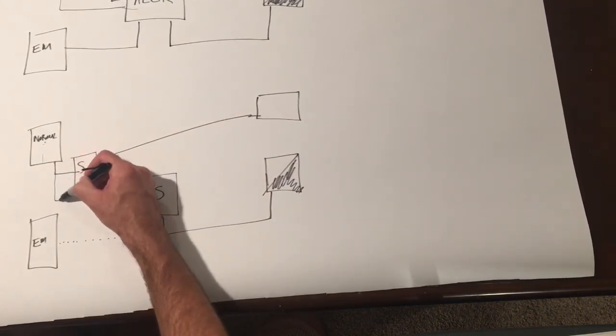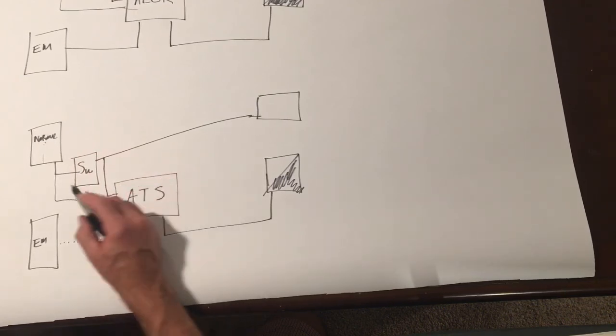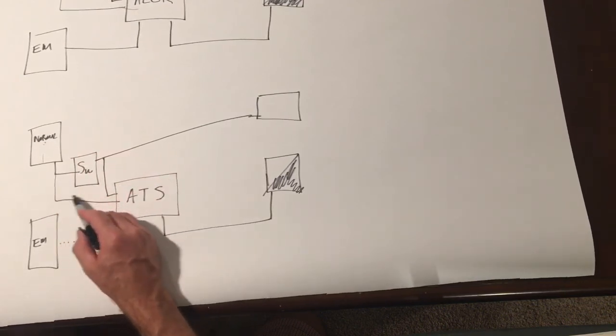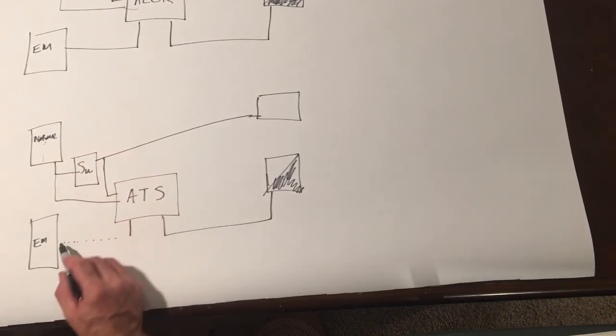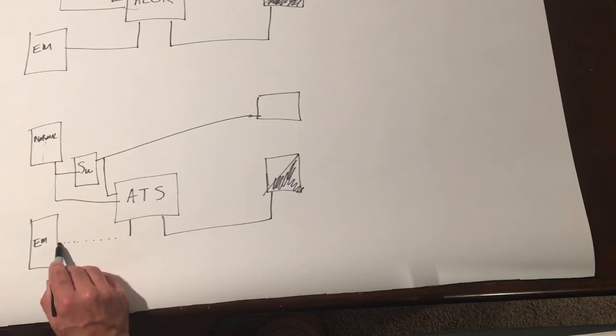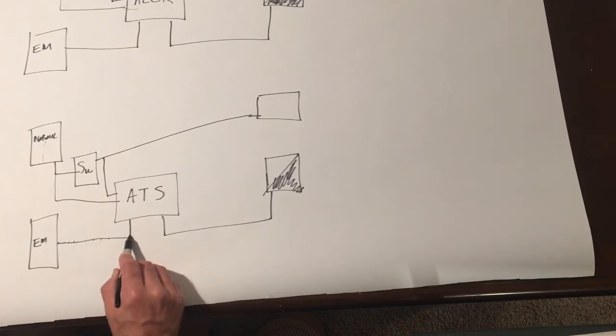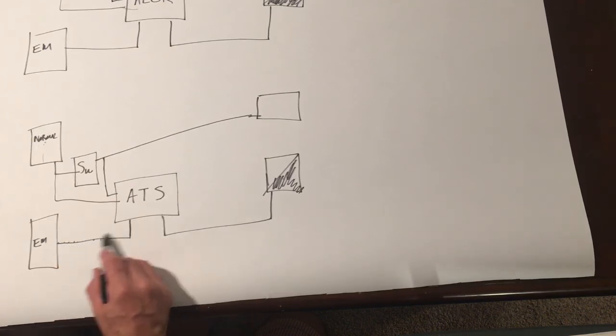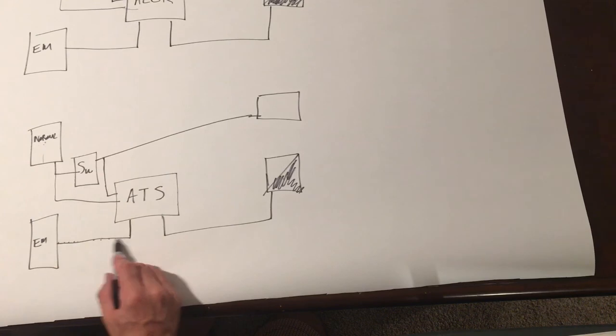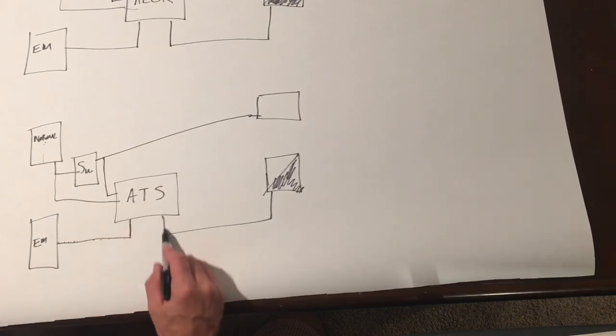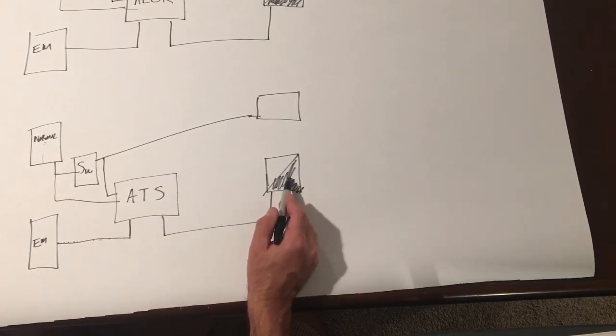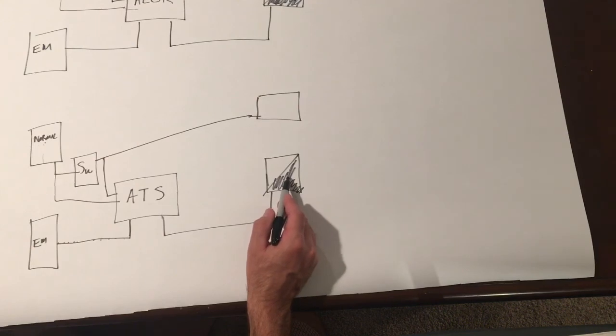We also have an unswitched hot coming in here. If we lose power, this goes away. And this is why I drew this dotted. This turns on. And now this emergency panel is now powering that fixture. So that's the third way of doing it.